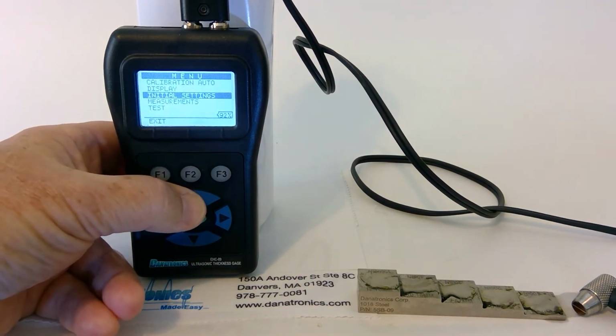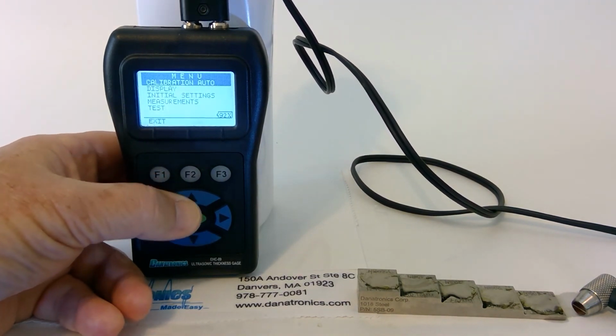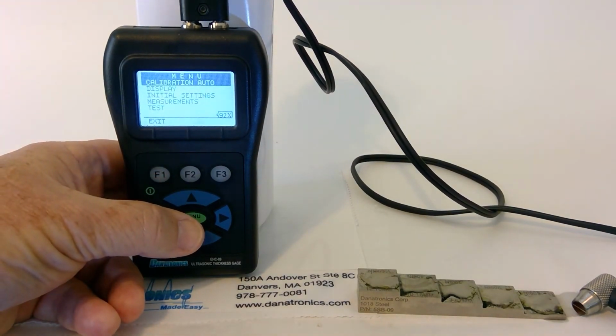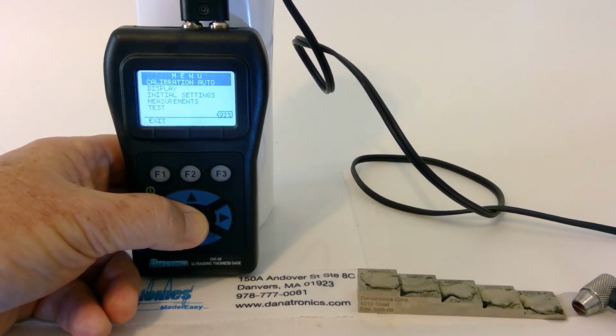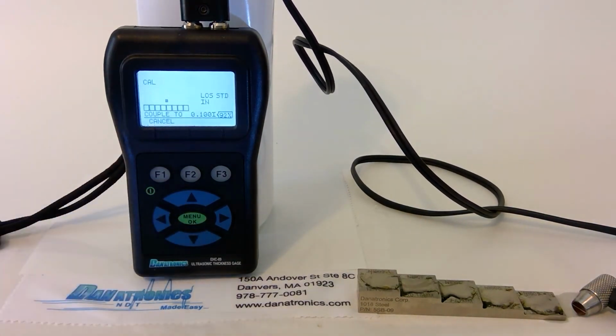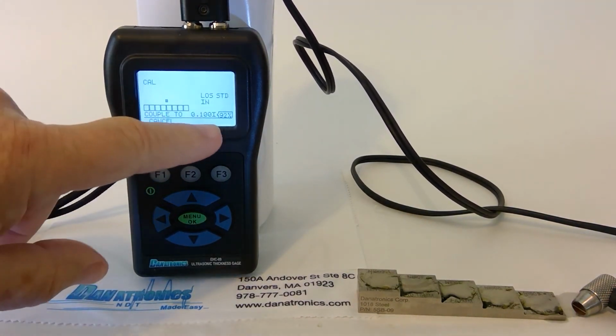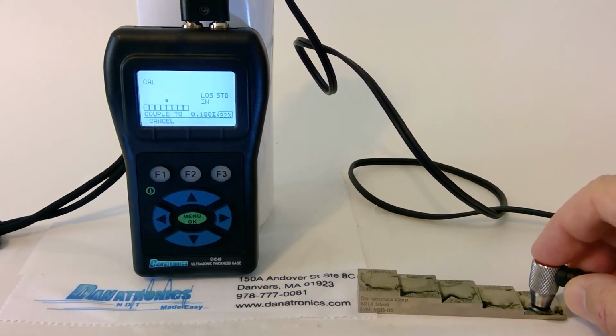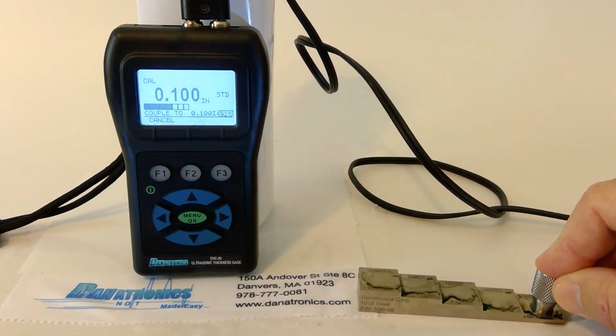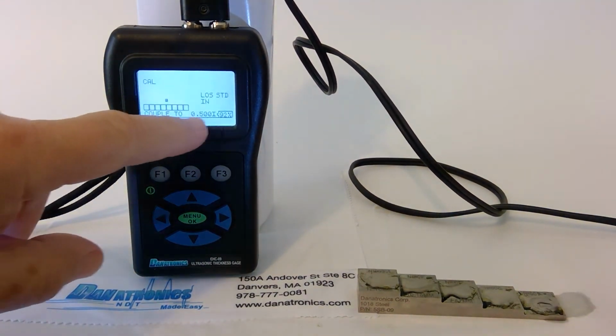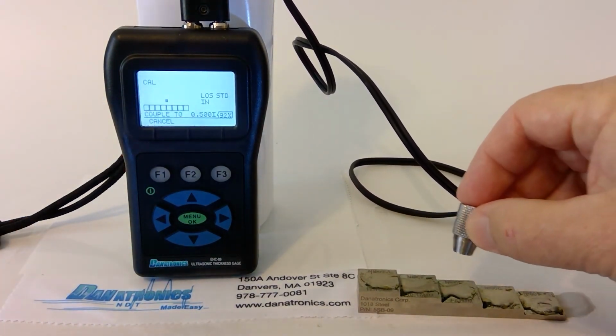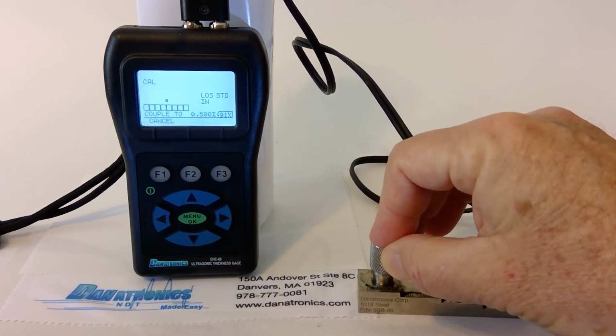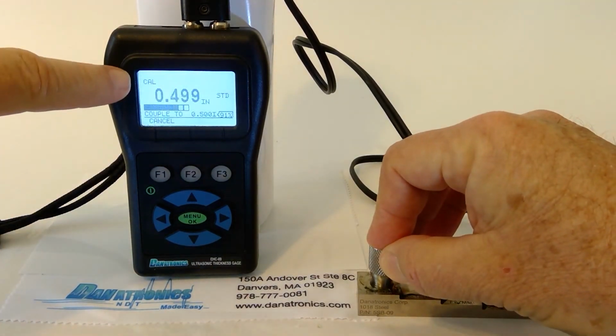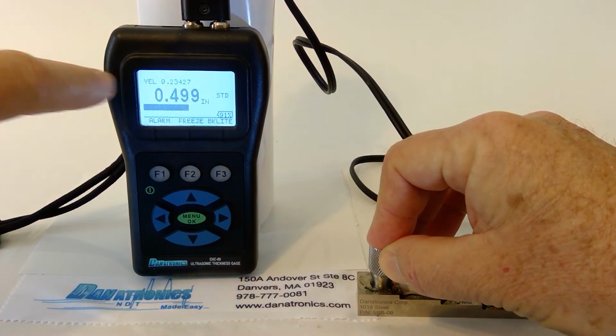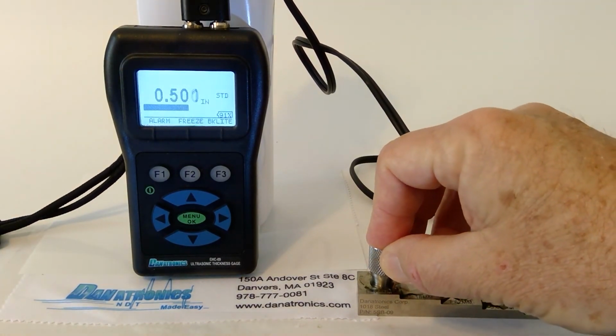We go back, highlight calibration. As you see, it has changed to auto. We hit OK. Now it asks us to couple to the 100 thousandth side of the block. The gauge beeps. Now it's asking me to couple to the 500 thousandth side of the block. Once this is completed, you will notice at the top, it calculates the velocity. And now we are calibrated.